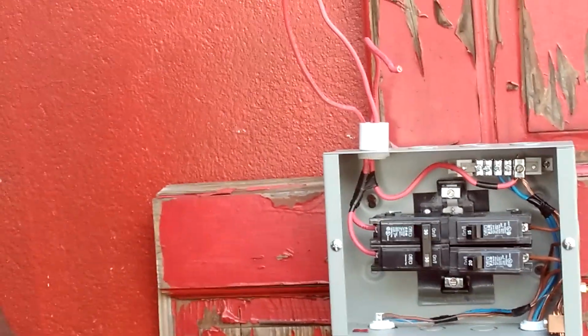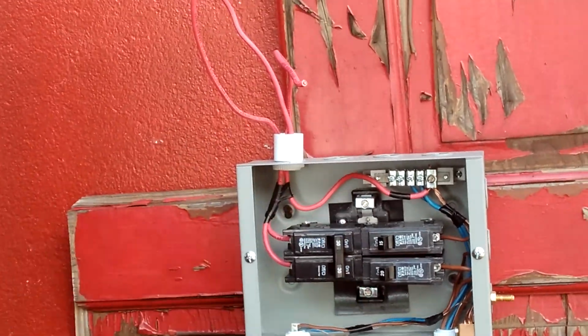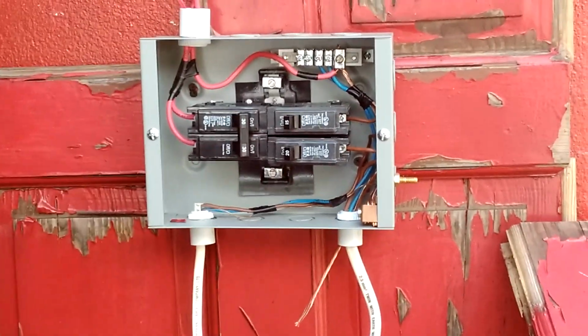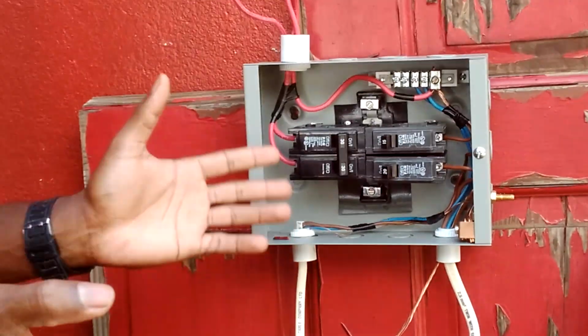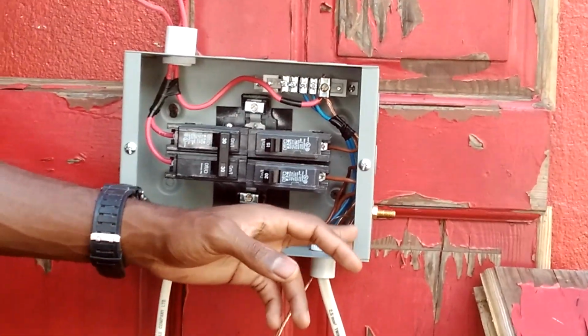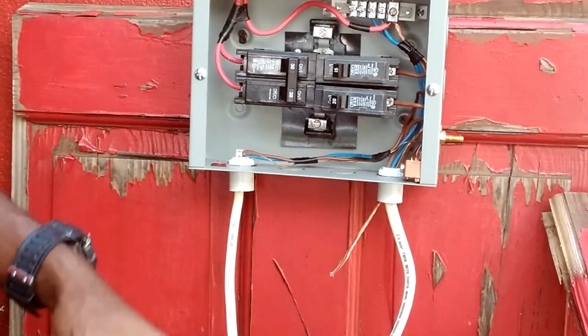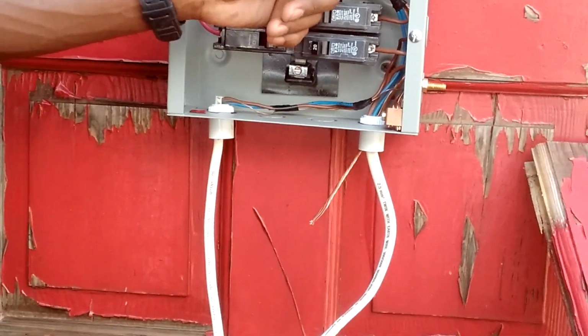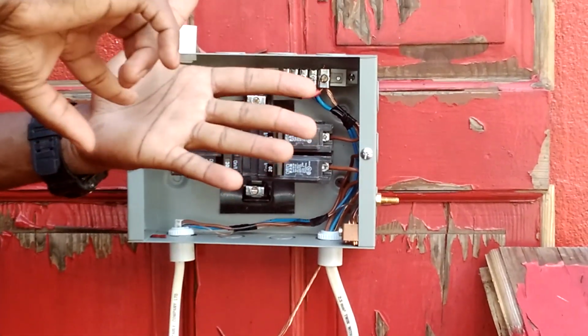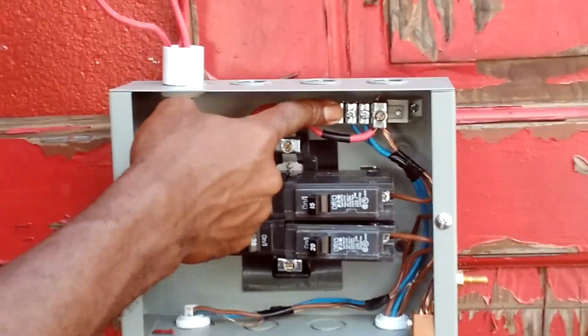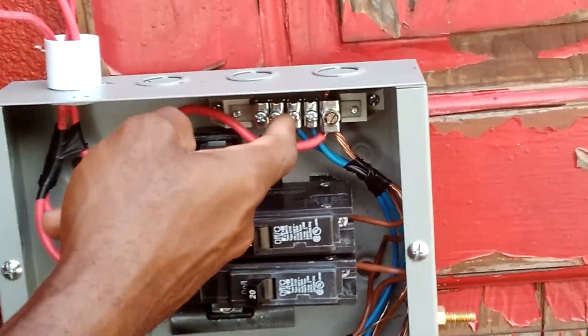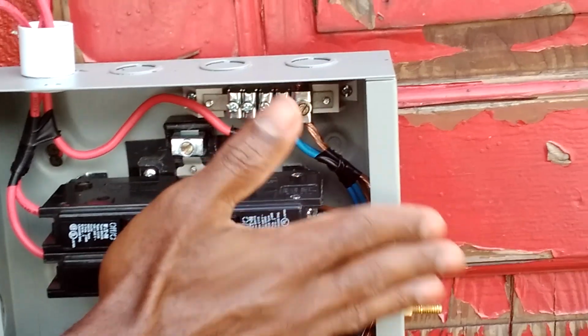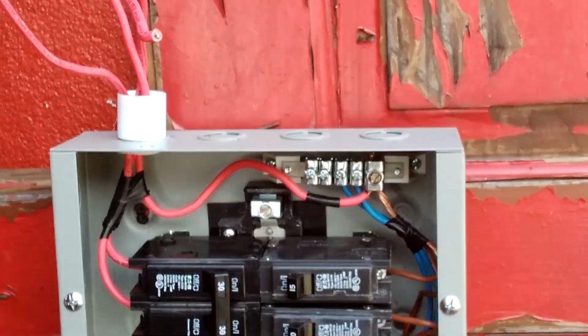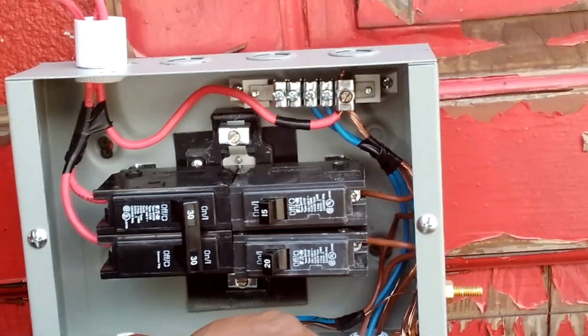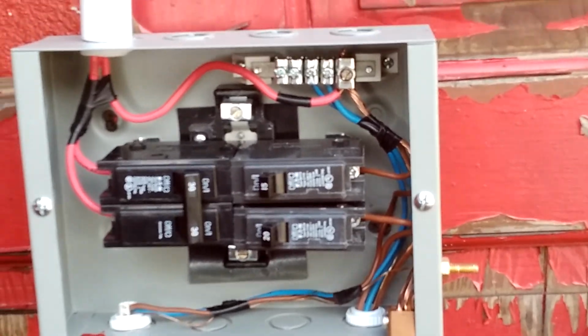Different countries use different standards where earthing is concerned. Overseas, according to my experience, we don't use a normal earth lug like this—we have what is called an earth screw. You put all the earth wires into the neutral bar, and you have a little screw that connects the neutral bar to the casing of the circuit breaker panel. That's how it's done overseas, but here in Jamaica, we use an earth lug. So that's the difference.